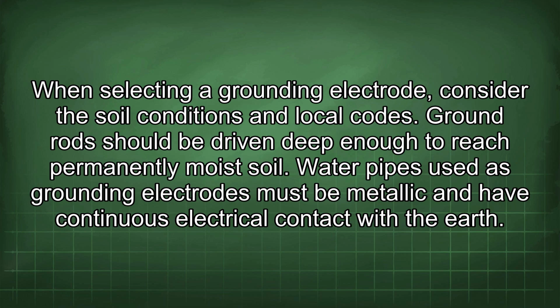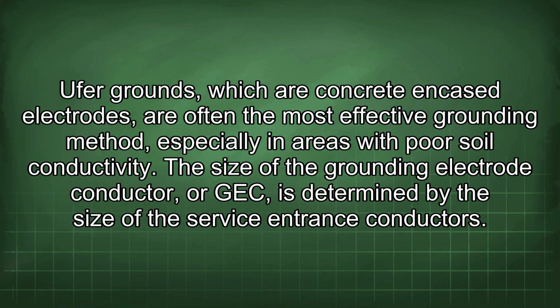When selecting a grounding electrode, consider the soil conditions and local codes. Ground rods should be driven deep enough to reach permanently moist soil. Water pipes used as grounding electrodes must be metallic and have continuous electrical contact with the earth. Ufer grounds, which are concrete encased electrodes, are often the most effective grounding method, especially in areas with poor soil conductivity.